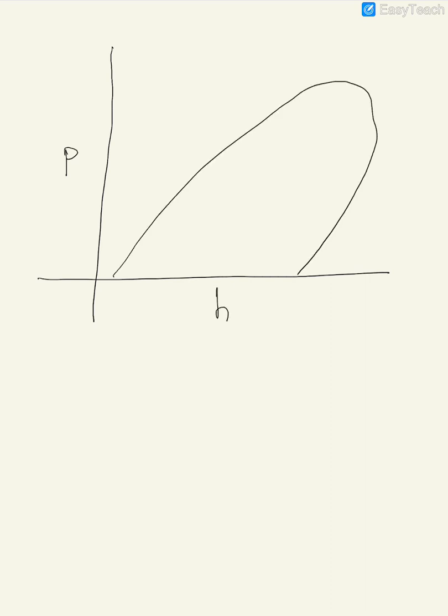So this is, let us say, the vertical, this is the horizontal, this represents the pressure, this is the enthalpy, this is the vapor dome. We are compressing the refrigerant from the evaporator pressure to the condenser pressure, and this is done in two stages. So in the first stage, compressor 1, you compress, then there is an intercooling in the flash intercooler, and then there is a compression again in the second compressor, and then there is a condensation.